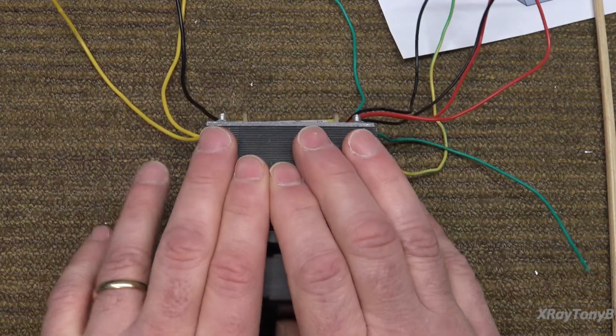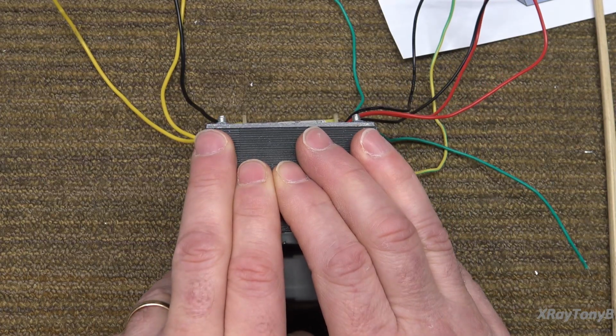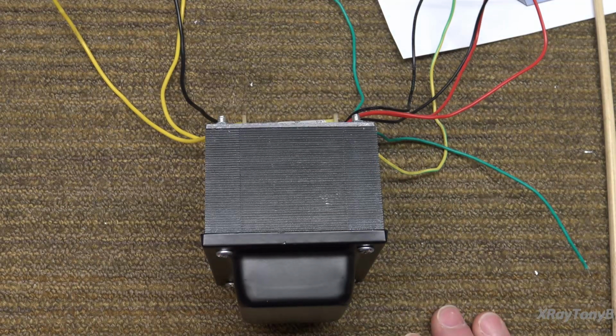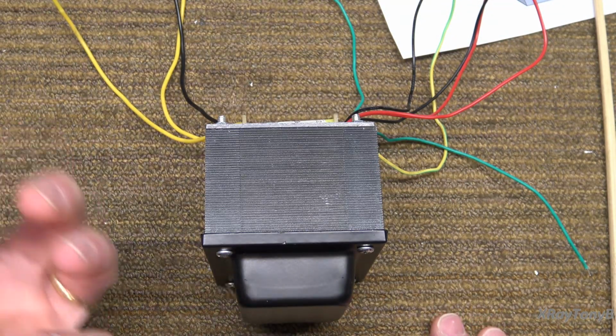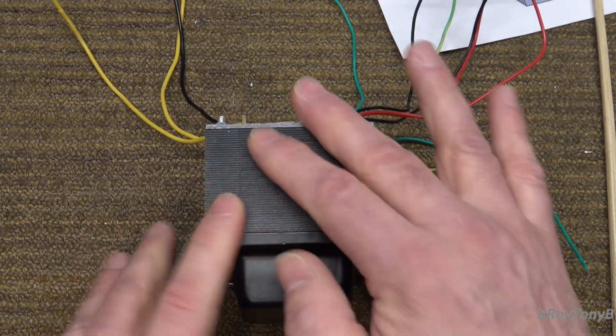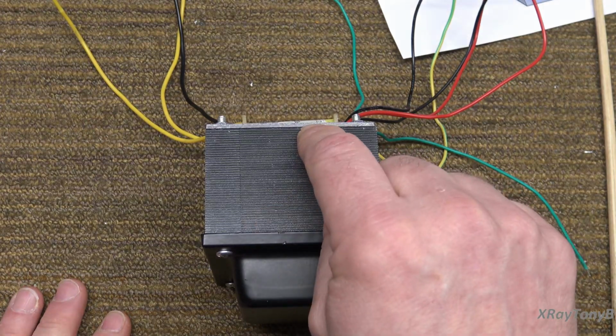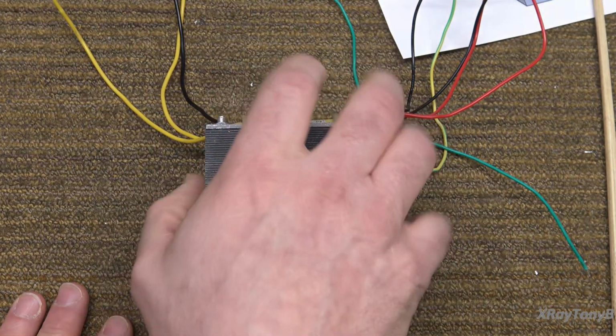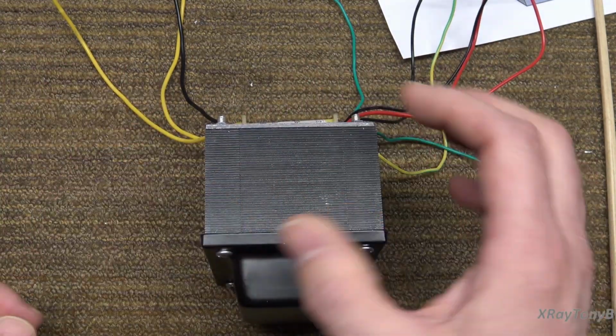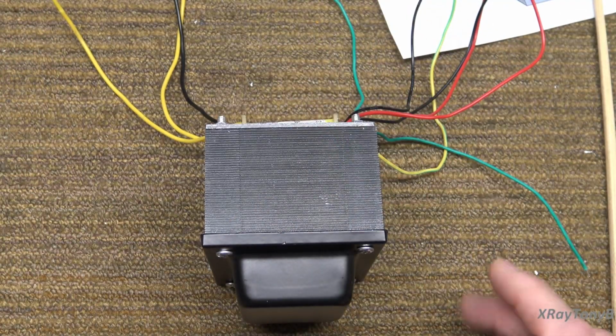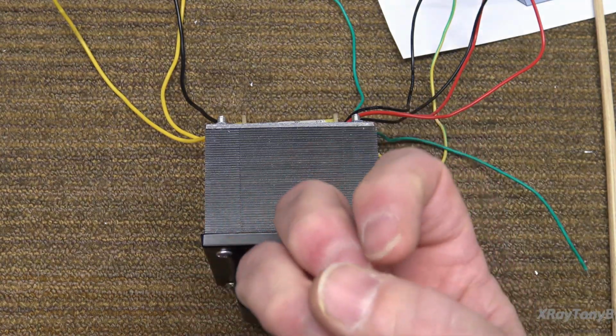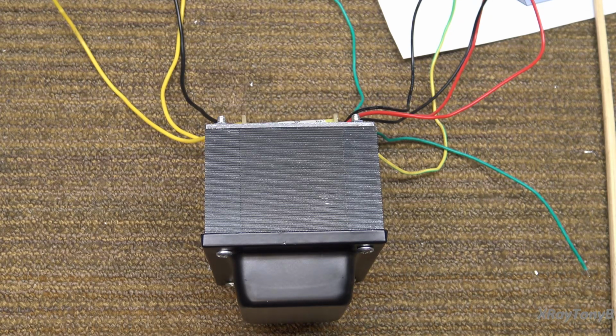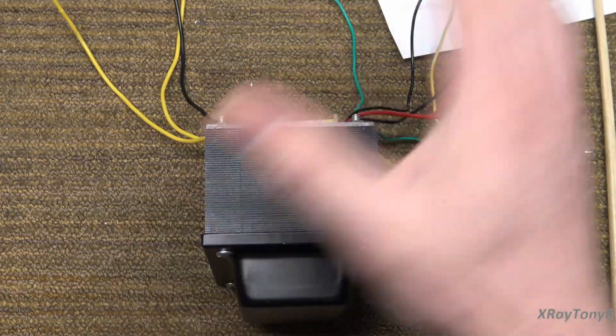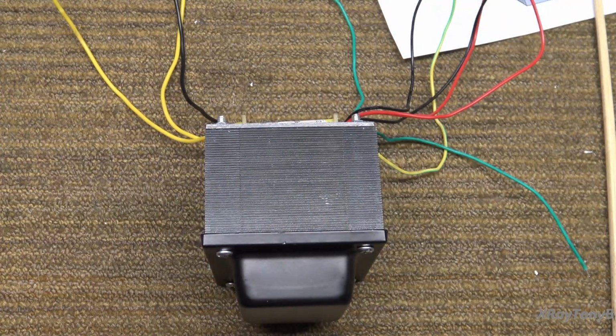As I said earlier in the video, this metal doesn't like to change the way it is. Whatever state it's in magnetically, it wants to stay there, and to change it you have to put a little bit of energy into it. There will be a delay from when you increase, for instance, from 0 volts to 10 volts, a delay from when that transformer is non-magnetic up to when it magnetizes to the level it would be at 10 volts. There's a delay there, and for that period of time it resists that. We call that reluctance. Since we're using AC, that's constantly happening, changing up and down, up and down. So that reluctance can really eat up a lot of your efficiency of the transformer.